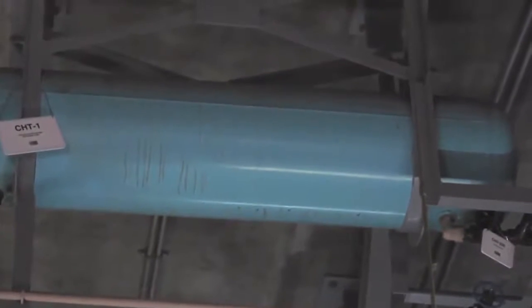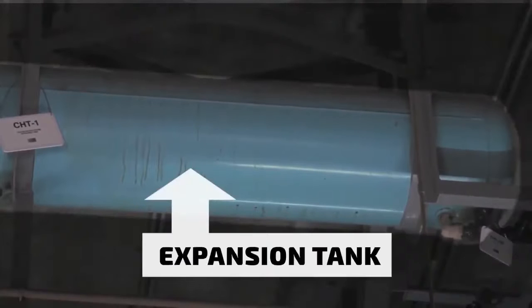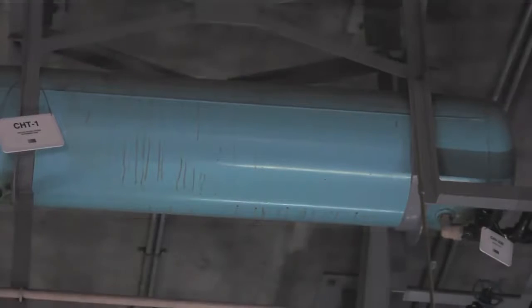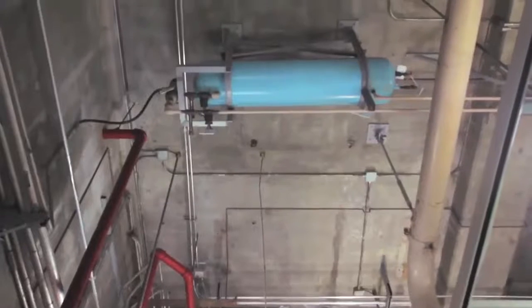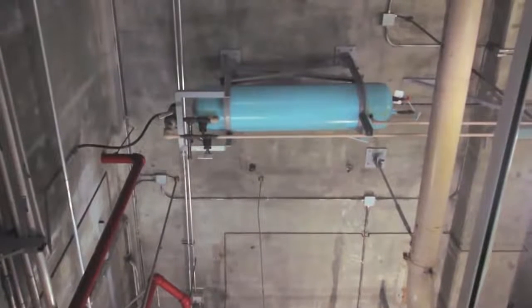In the overhead, we have an expansion tank. The expansion tank is a volume that allows makeup for normal temperature fluctuations and leakage. It is also elevated to allow better suction pressure to the pump.